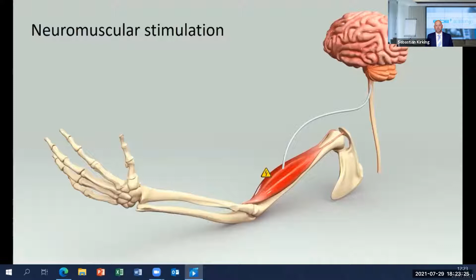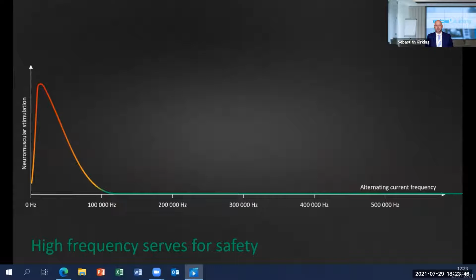To heat up the tissue effectively, the current must be high enough. Electric current, though, can be very dangerous, as it usually causes neuromuscular stimulation. And this is true for direct current, DC, but even more for alternating current, AC. The reason why the patient is not electrocuted is that electrosurgical generators use alternating current with high frequency. As the graph shows, the most dangerous frequency is somewhere around 100 to 1000 hertz.